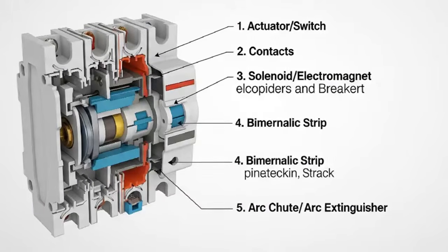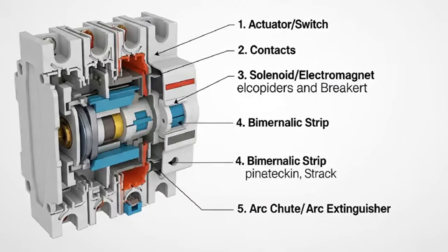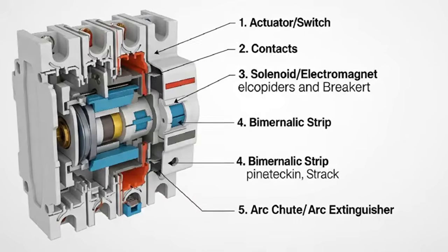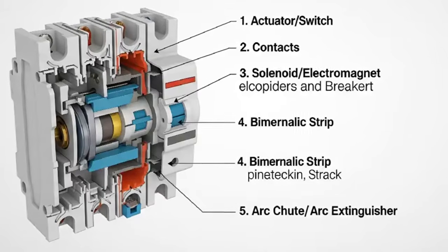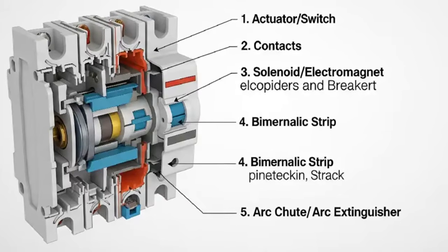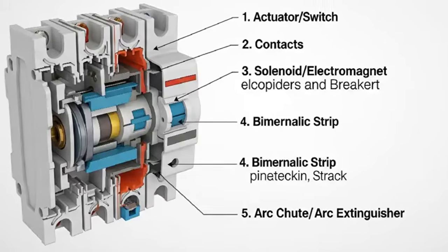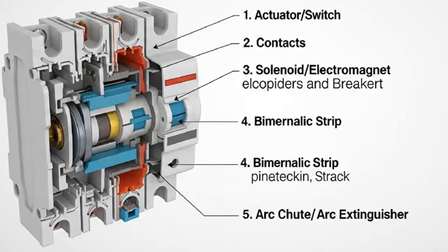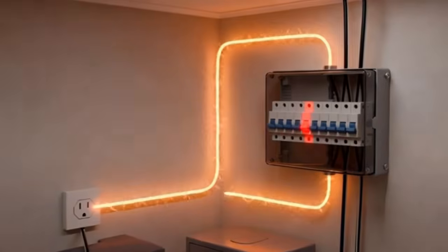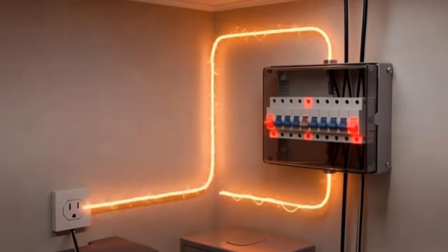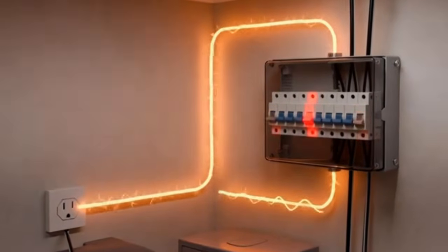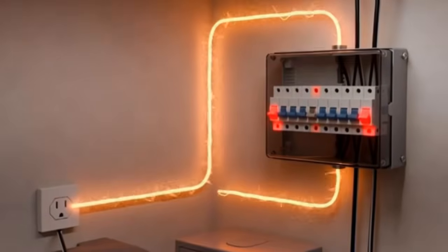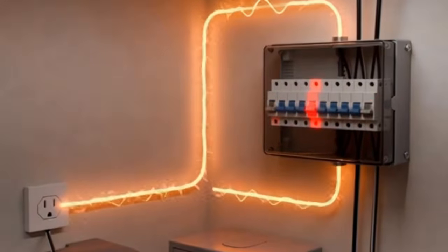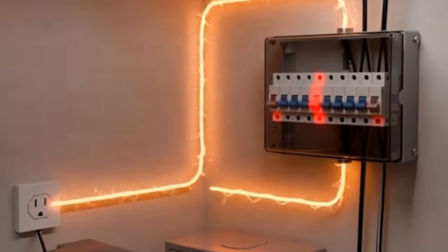The internal mechanism may be stuck. The contacts may be welded together from previous arcing. The trip mechanism may be physically broken. You can sometimes identify a failed breaker by its physical condition. Does the handle feel loose or wobbly? Does it move differently than other breakers in the panel? Is there discoloration or melting on the breaker face? Do you smell burning near that breaker?